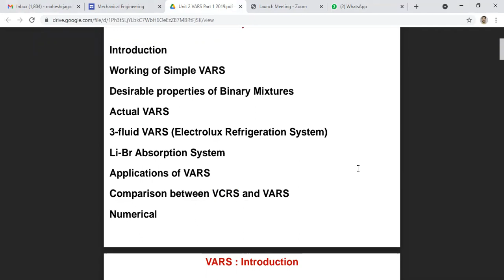So first of all, we are going to see the introduction of vapor absorption system. Basically, vapor absorption refrigeration system belongs to the class of vapor cycle, similar to the vapor compression system. However, unlike vapor compression refrigeration system, the required input to absorption system is in the form of heat. Hence, these systems are also called heat operated or thermal energy driven systems. Since the conventional absorption system uses liquid for absorption of refrigerant, these are also sometimes called wet absorption system.